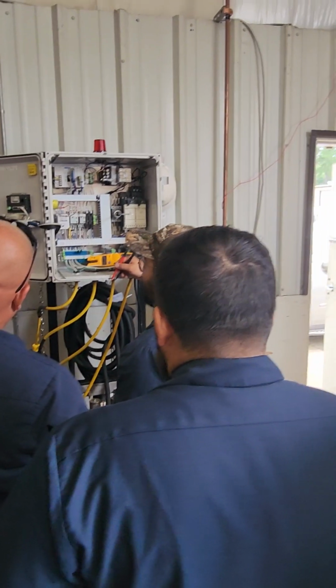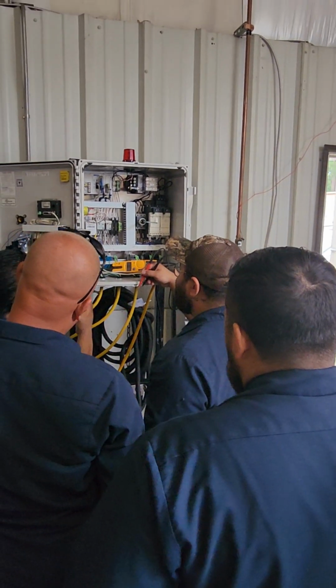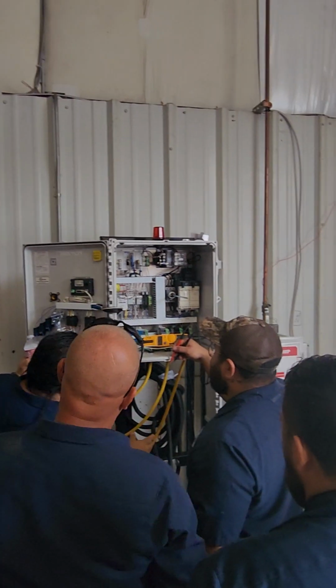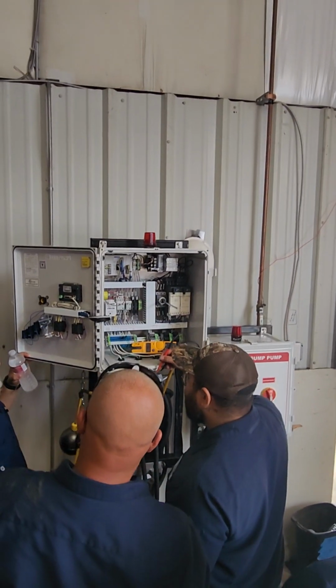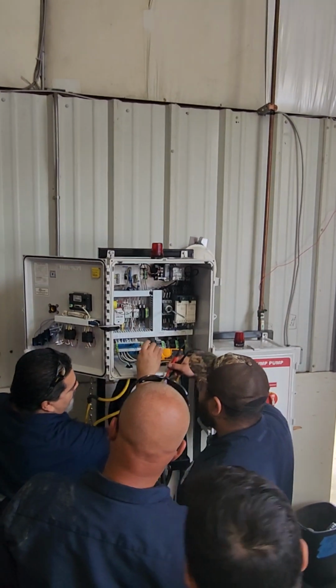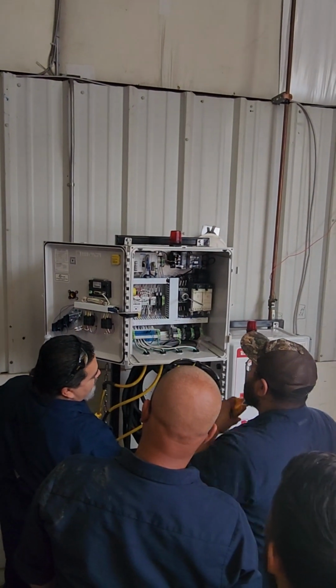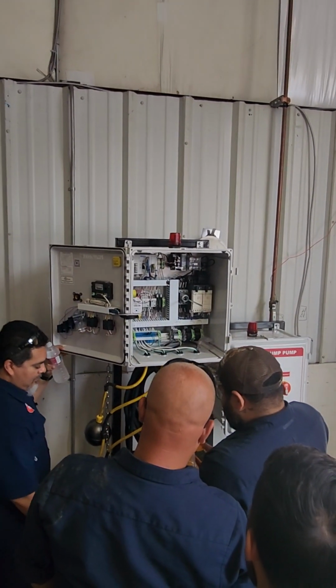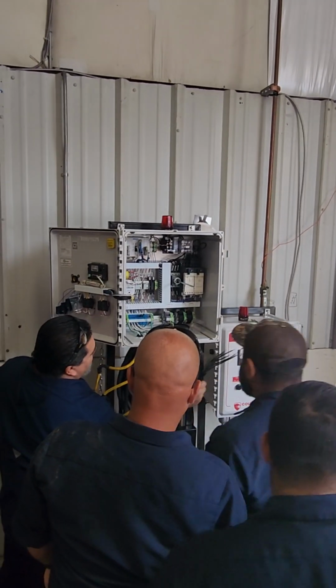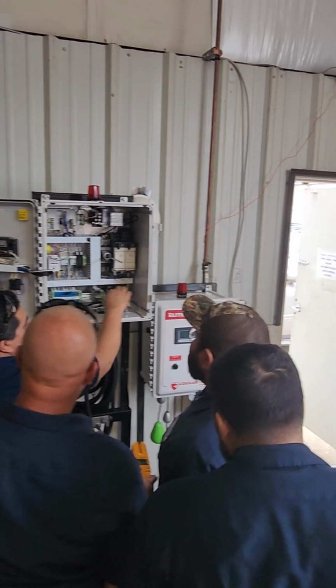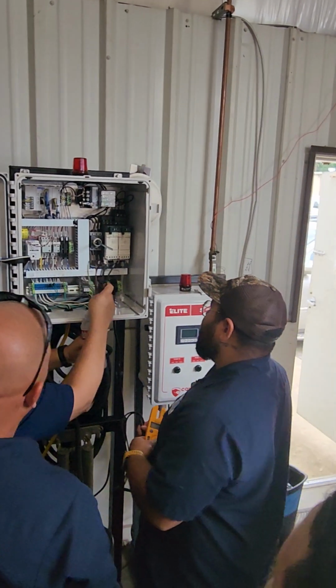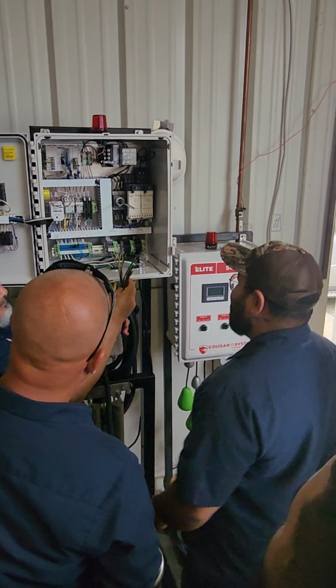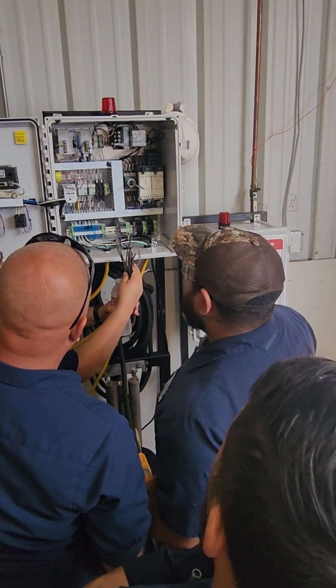Yeah. But yes. The other thing, of course, so you check your floats and all of that, right? So that's how you check continuity. Now, to check your amperage, you know how to check your amperage. It's on the motor. Now your motor normally, for example, this has black terminals, so it would be hooked up here instead of directly to the motor. So how will you check your amps based on the pump?